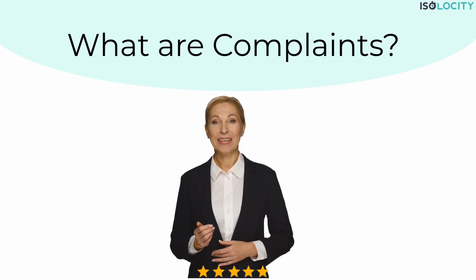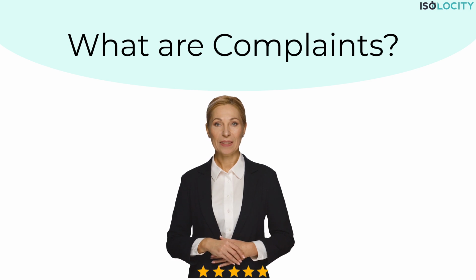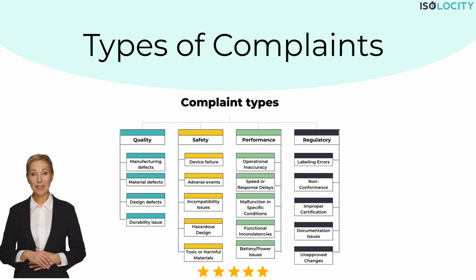A complaint is any expression of dissatisfaction related to a product's quality, safety, performance, or regulatory compliance. In the context of ISO 13485, complaints specifically refer to issues users, customers, healthcare providers, or regulators raise after the product reaches the market. Understanding the different types of complaints helps in prioritizing their resolution and setting appropriate corrective actions. Here are the main types of complaints.